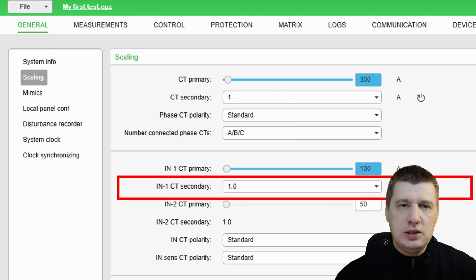While your phase CTs watch the heavy load, this input is connected to terminals A13 and A14 to catch ground fault current leakage. Depending on the CTs you installed, the P5 allows you to configure this for 1 amp, 2 amps or 5 amps. However, if you're using the very sensitive earth fault version of the relay, these settings are fixed at 1 amp. Why then use 1 amp?